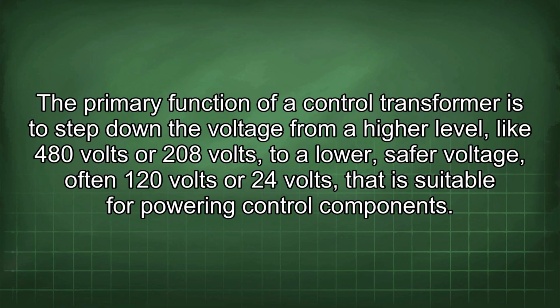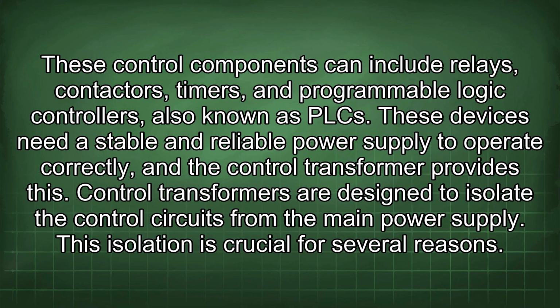The primary function of a control transformer is to step down the voltage from a higher level, like 480 volts or 208 volts, to a lower, safer voltage of 120 volts or 24 volts that is suitable for powering control components. These control components can include relays, contactors, timers, and programmable logic controllers, also known as PLC. These devices need a stable and reliable power supply to operate correctly, and the control transformer provides this.